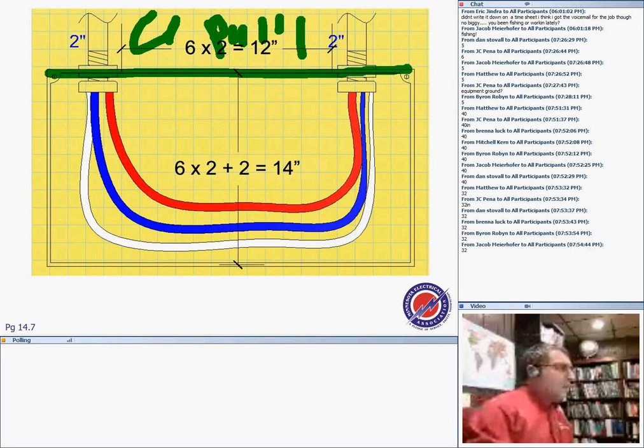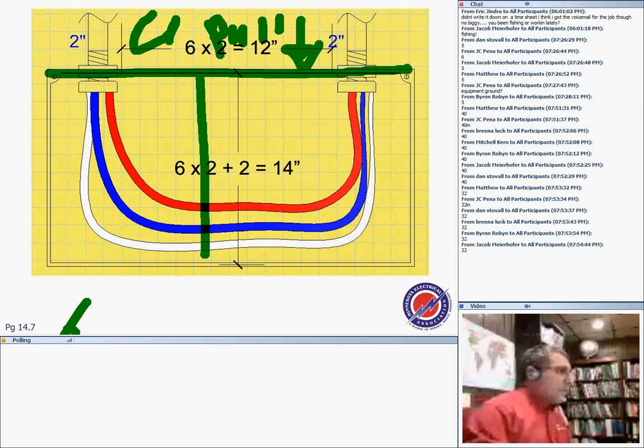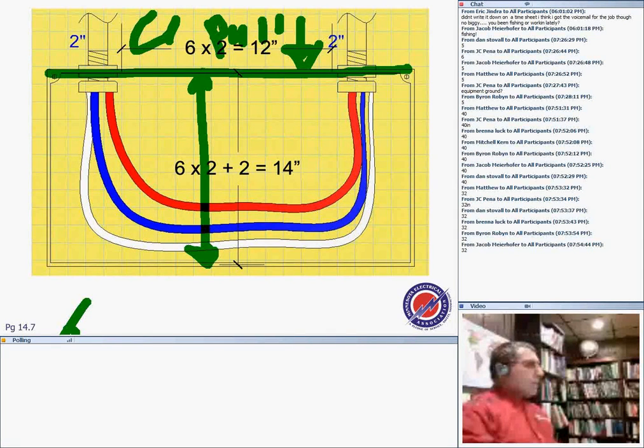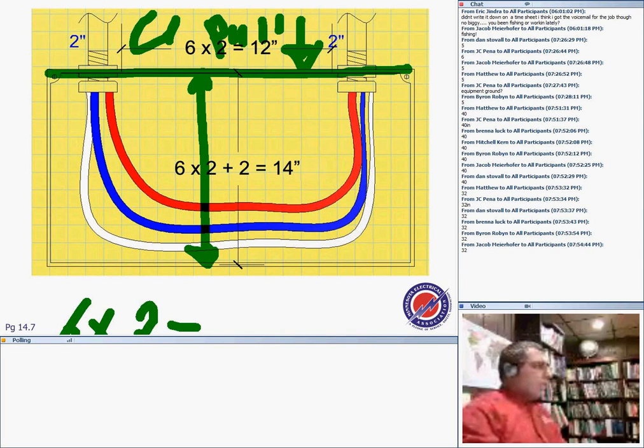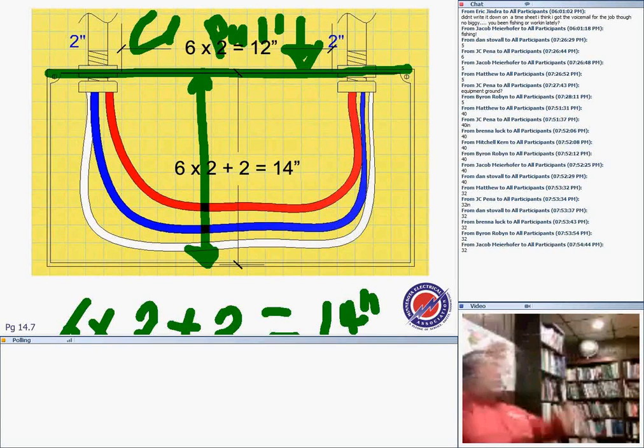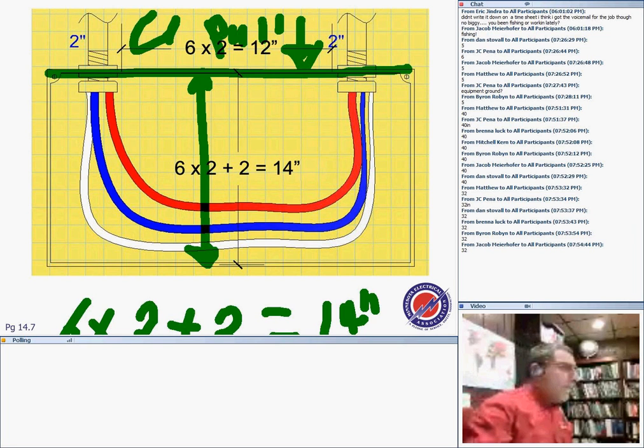So look at it from this way, 6, so that will get you the opposite junction to the opposite wall to where you entered. So code says always multiply by 6 times the largest conduit engaged to every other conduit sharing the same wall, 2. That'll get you 14. Any questions how they came up with 14 inches?